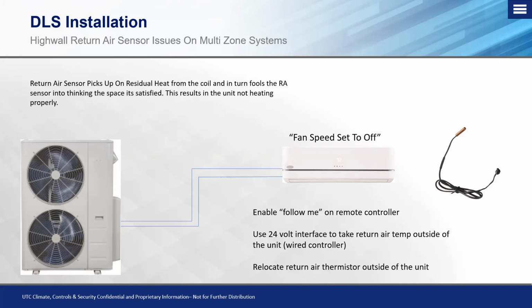If you have a system that has a 24-volt interface and you need to configure the fan speed to shut off after set point, the nice part about that 24-volt interface is that it takes temperature from your third-party wired thermostat on the wall as a default. So it's not taking the return air temperature. So you already have something taking external temperature outside of the unit. So you don't have to relocate the return air thermistor. The only thing that you would have to do with that application is just shut the fan speed off after set point, which is done through your wireless handheld remote controller.